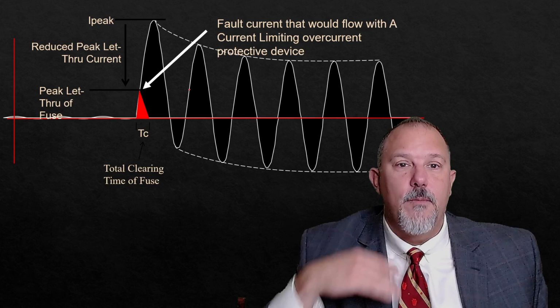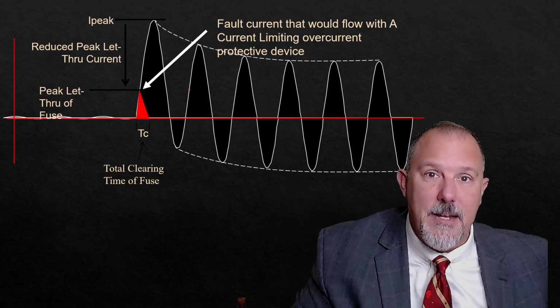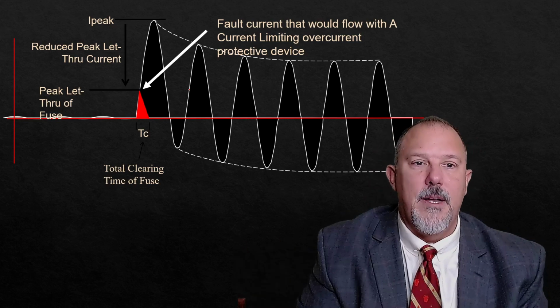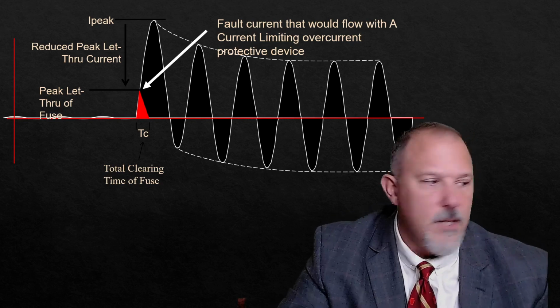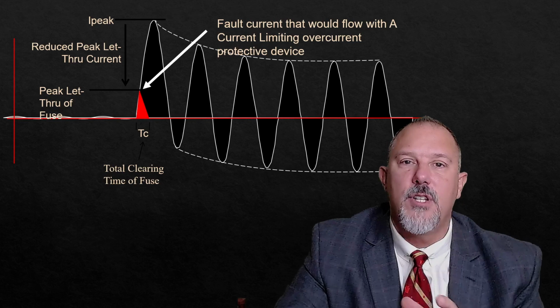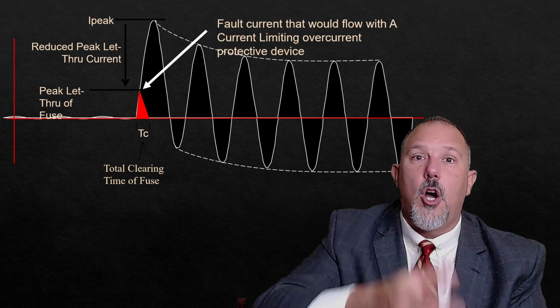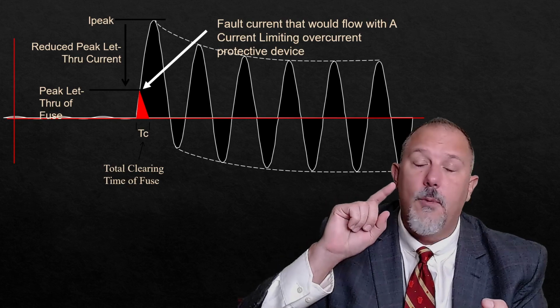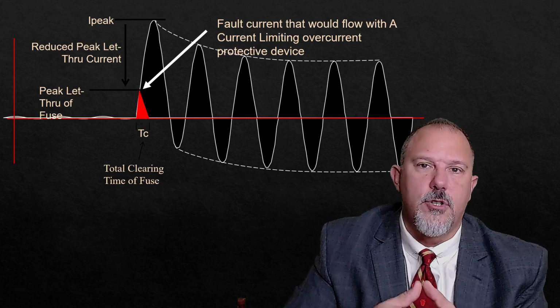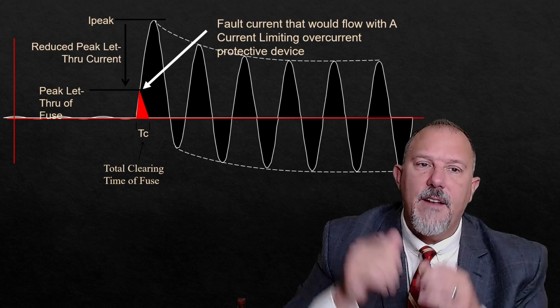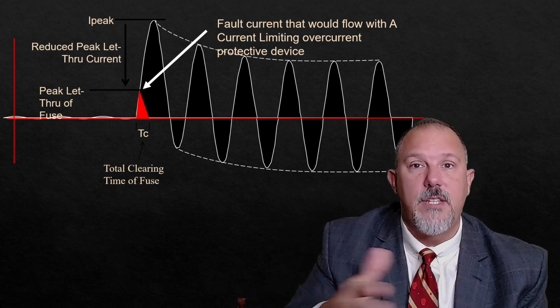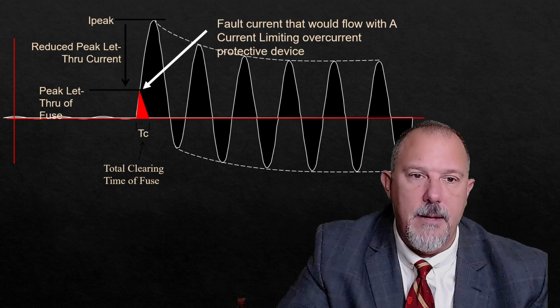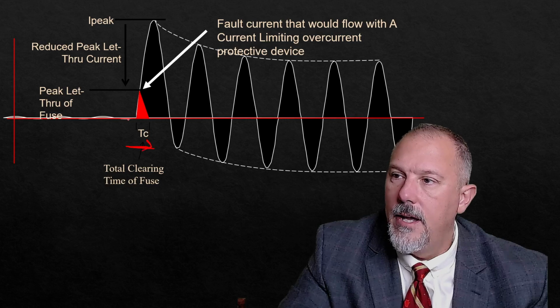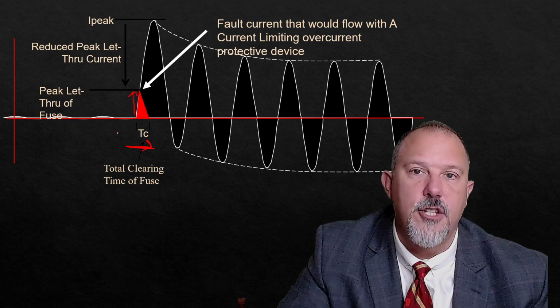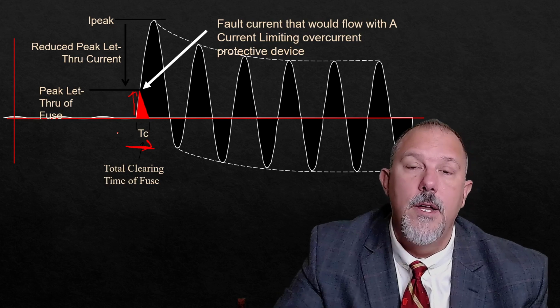Short circuit current ratings. So current limitation. When I talk about current limiting devices, I want to reduce the peak. What does that do to a system? When I reduce the peak current, I reduce the magnetic forces and the amount of heat that power distribution system components are seeing, whether it be your terminations, equipment, conductors, busway, terminal blocks. If I could, that first half cycle is a doozy. It will do the most damage. It's the rate of change for a very short period of time. Here, in that direction, I have a very rapid increase in change of current. During a short circuit current, that first half cycle does a lot of damage.